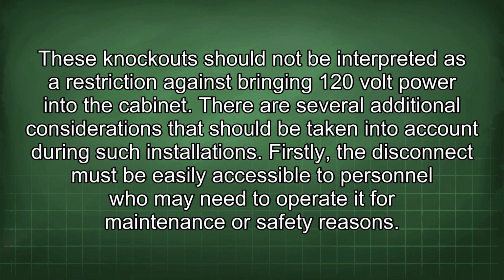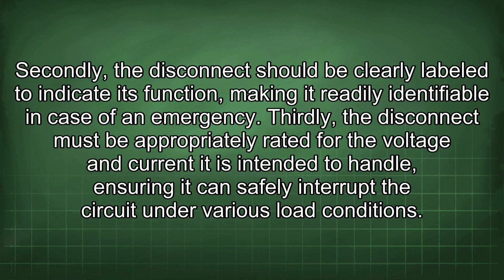Firstly, the disconnect must be easily accessible to personnel who may need to operate it for maintenance or safety reasons. Secondly, the disconnect should be clearly labeled to indicate its function, making it readily identifiable in case of an emergency. Thirdly, the disconnect must be appropriately rated for the voltage and current it is intended to handle, ensuring it can safely interrupt the circuit under various load conditions.